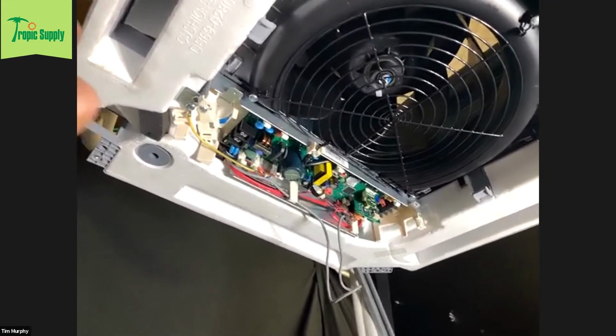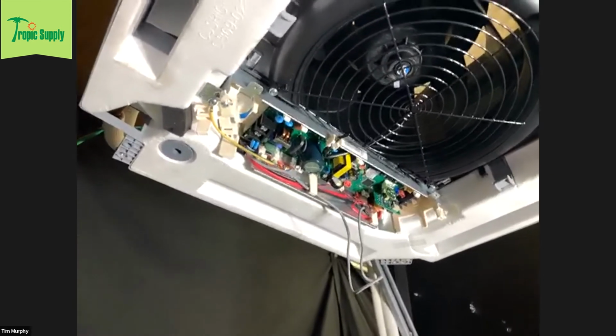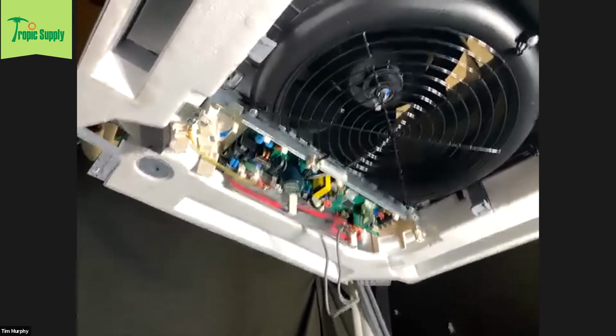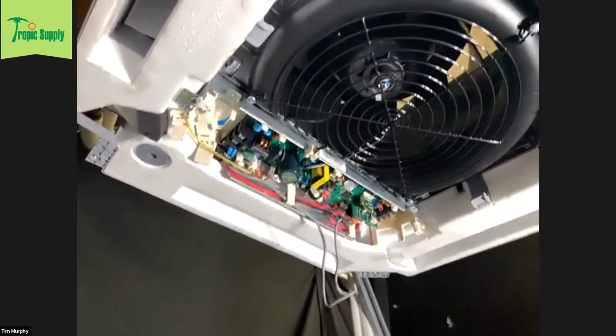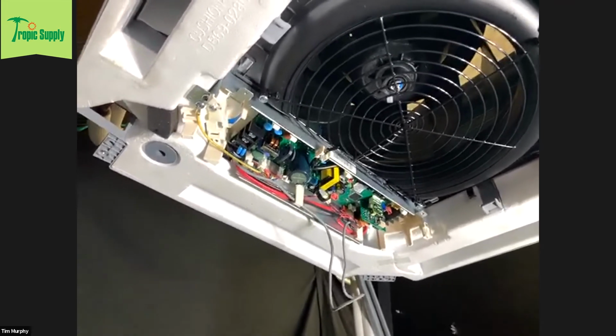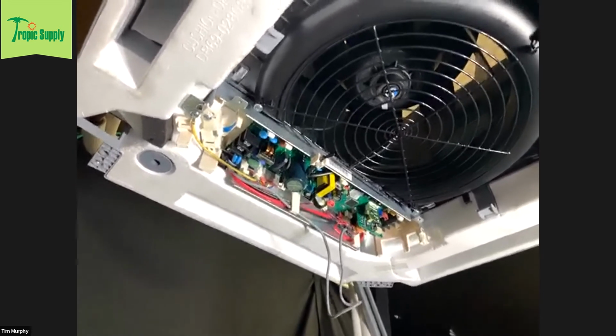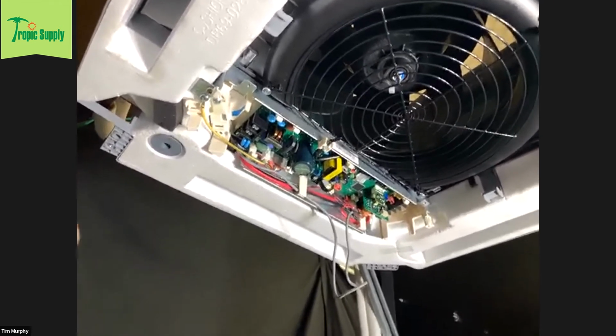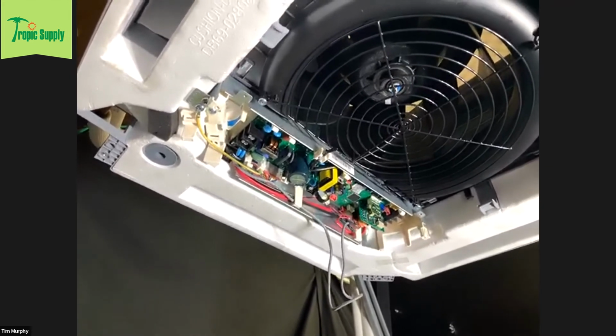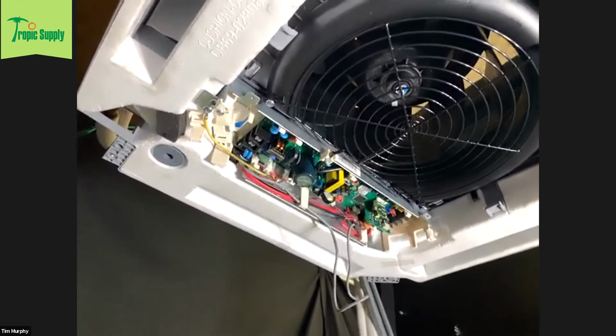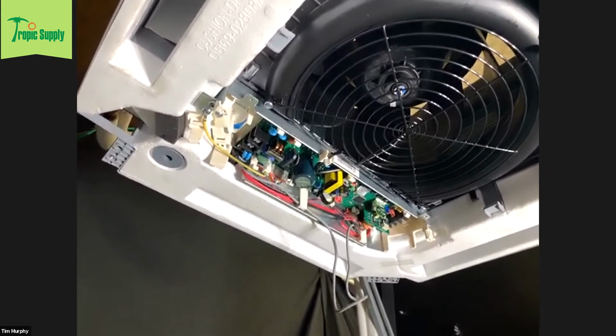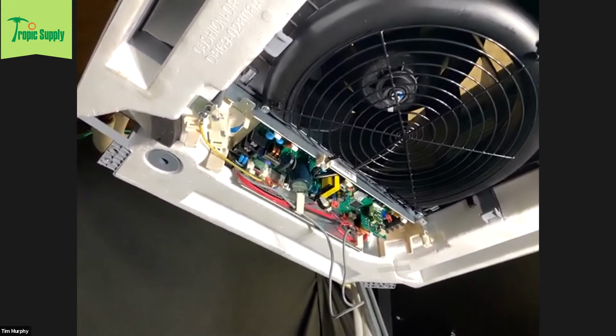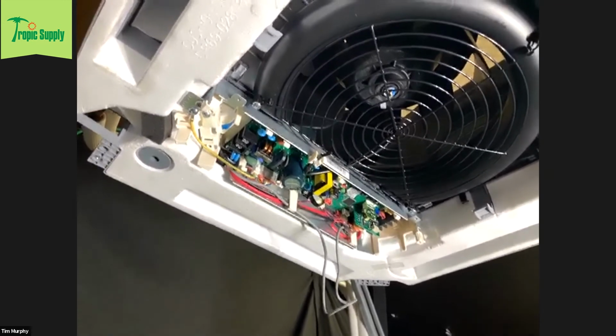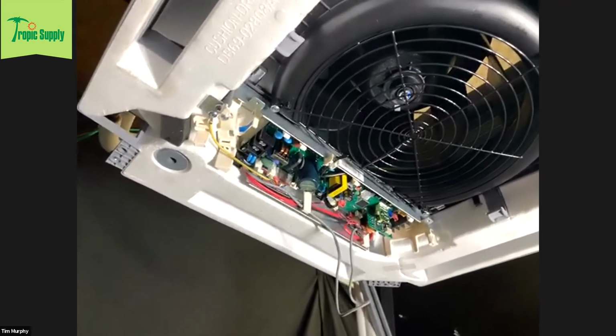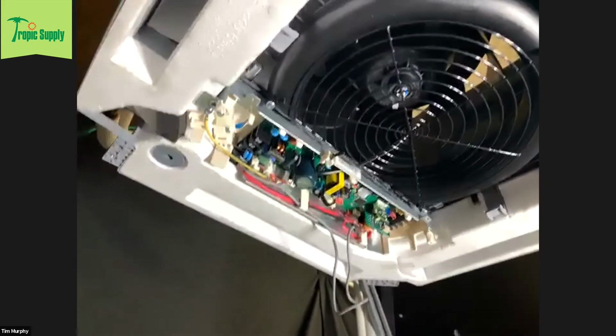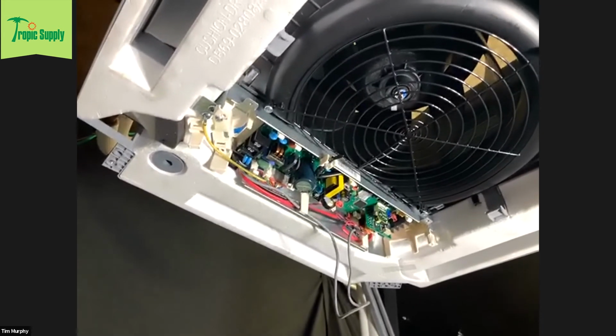Now, that being said, there have been circumstances in the past where a contractor didn't have access to 16-2 shielded. Then he used an 18-2 shielded, and yes, it worked. Another thing to point out is that shielded wire should be a stranded wire. But per Samsung's recommendation, and they really emphasize to us that it is that 16-2 shielded control wire. Will the 18-2 shielded control wire work? Yes, it may work, but per recommendation from the manufacturer, 16-2 continuous shielded wire.